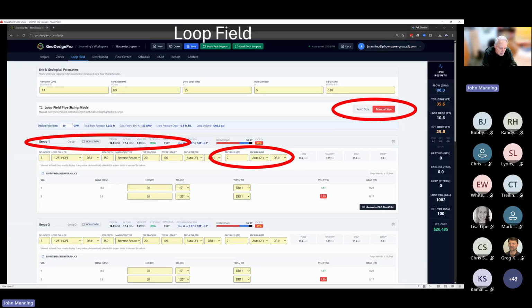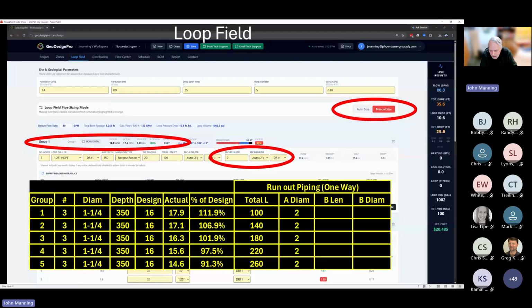So let me sort of summarize this in a table. We've got our 5 groups with 3 bores in each group. They're technically all identical, so the design flow rate for each of those groups is 16 GPM. The program tells you the actual GPM, and then I calculated the percent of deviation from design.